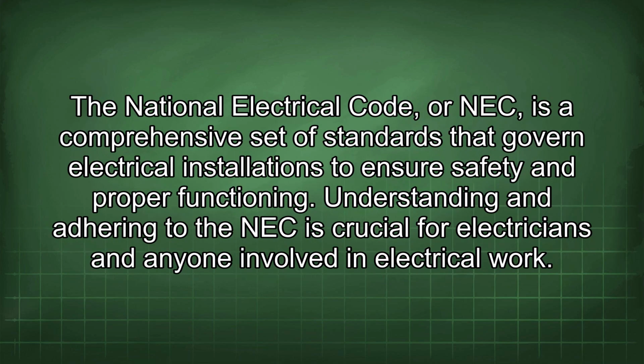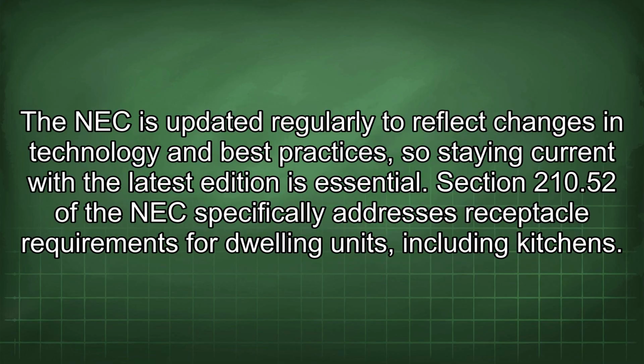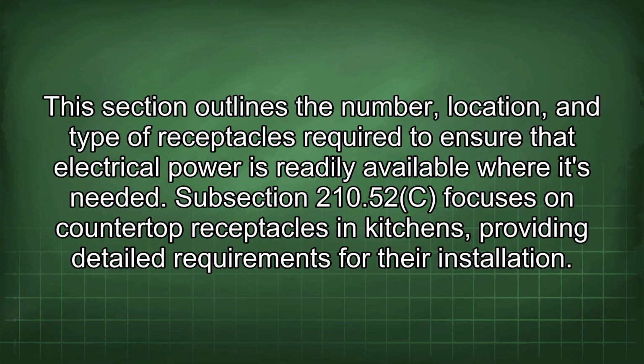The National Electrical Code, or NEC, is a comprehensive set of standards that govern electrical installations to ensure safety and proper functioning. Understanding and adhering to the NEC is crucial for electricians and anyone involved in electrical work. The NEC is updated regularly to reflect changes in technology and best practices, so staying current with the latest edition is essential. Section 210.52 of the NEC specifically addresses receptacle requirements for dwelling units, including kitchens. This section outlines the number, location, and type of receptacles required to ensure that electrical power is readily available where it's needed. Subsection 210.52C focuses on countertop receptacles in kitchens, providing detailed requirements for their installation.